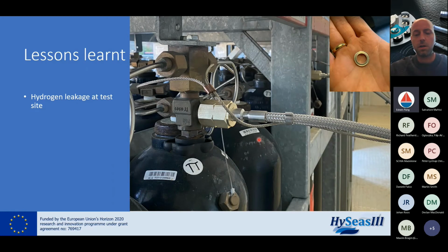As Hans mentioned regarding the gas sensors, they are all located in the gas tank containers and the fuel cell containers, in places where it's possible for hydrogen to accumulate. And the system is built for ventilation, both the fuel cells and the gas container, so that the hydrogen is expected to leave the area. It rises up quite fast, approximately 25 meters per second when it's released. So it's important to handle the leakages when they do occur.